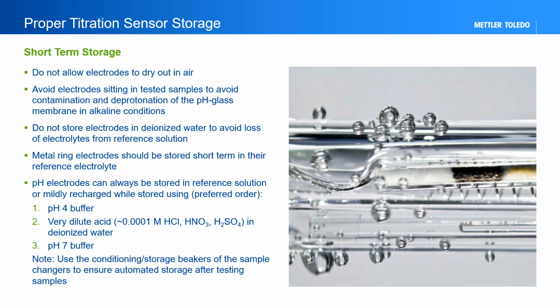A very dilute acidic solution in water, or in addition to the reference solution, can also be used. Even a pH 7 buffer can be used for a storage solution and may be preferred over a dilute acidic solution when testing for very low levels of acid or base to help avoid sample contamination. The park function of a titrator and sample changer allows for automated storage in a designated solution after a series of samples are finished being analyzed.